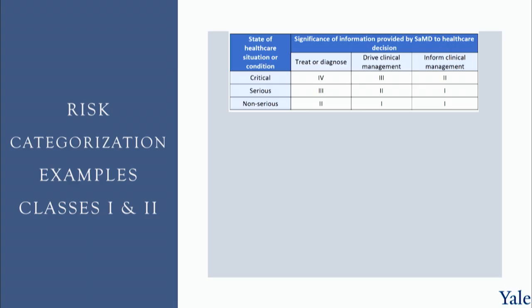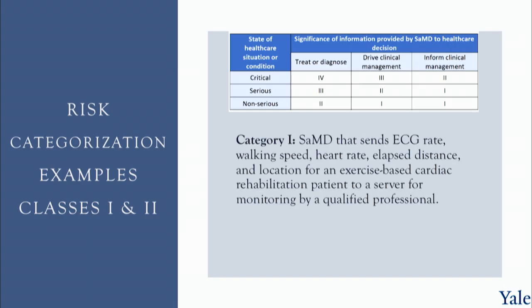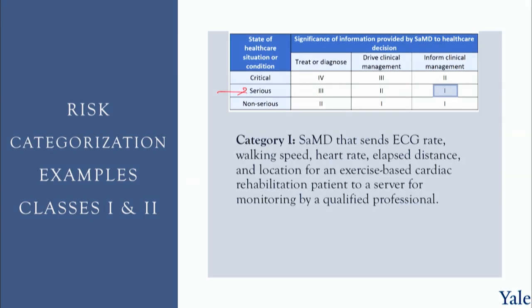Here is a Class 1 device example from the IMDRF documentation: software that sends ECG rate, walking speed, heart rate, elapsed distance, and location for an exercise-based cardiac rehabilitation patient to a server for monitoring by qualified professionals. We have a sensor, get measurements of what the patient is doing, and send them out. While the patient's cardiac condition is serious, the software is only informing clinical management — used together with lots of other information to ultimately make decisions.